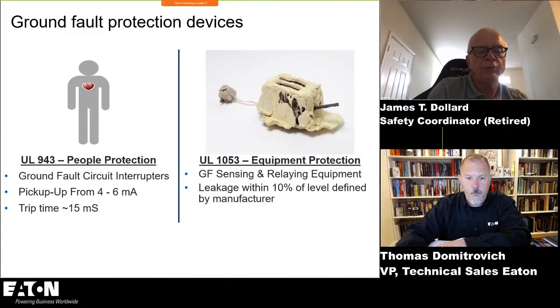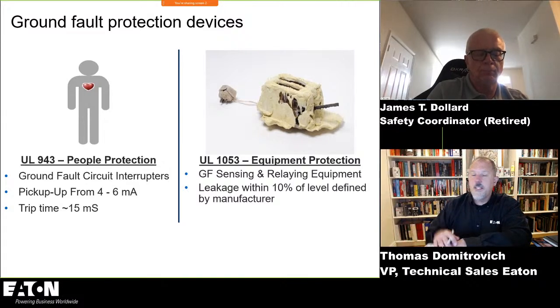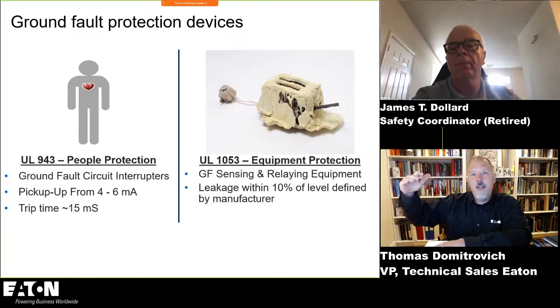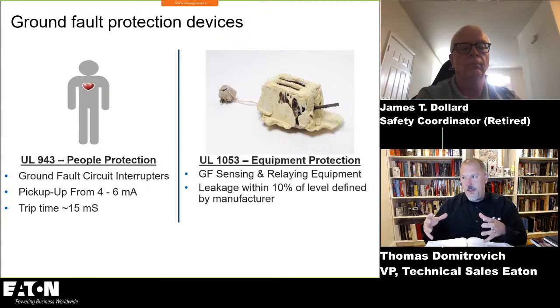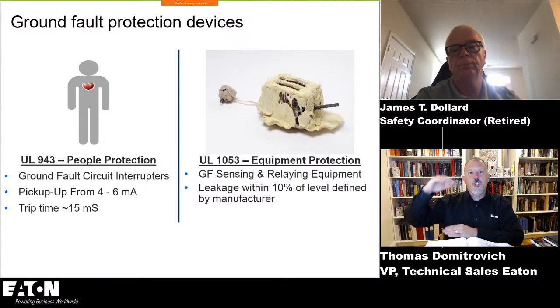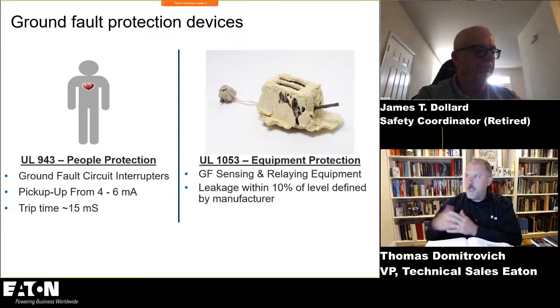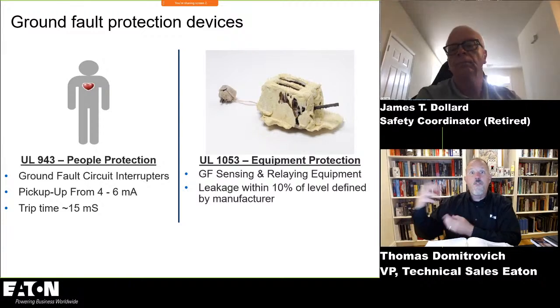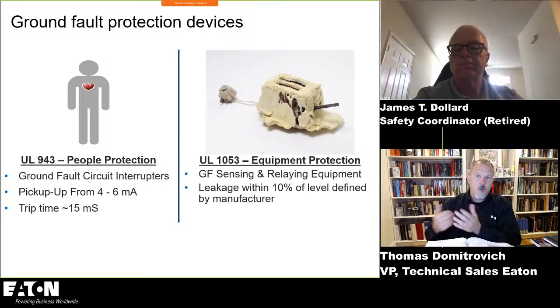Yeah. So what was the term that they tried to use? Was it special purpose GFCIs? Yeah, so that was the special purpose GFCI device, and we talked a little bit about that in our last session and on Monday as well. They go at a higher level, but the whole drive around that is that you control the amount of voltage across the human body, and if you can control that voltage potential via an assured equipment grounding path and all this other good stuff, then you know how much current would flow, and then you can provide some level of protection to keep the heart from going into defib, or even try to keep it below that let-go threshold. But there's a lot of other little aspects.